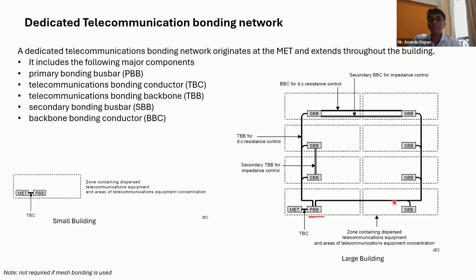When you have two different PBBs, that is primary bonding bus bars, in an electrical installation, you are not supposed to connect between two primary bonding bus bars. It's good not to connect them, because there can be circulating currents if there are leakages. So you isolate one telecommunication bonding network from another unless they are communicating.